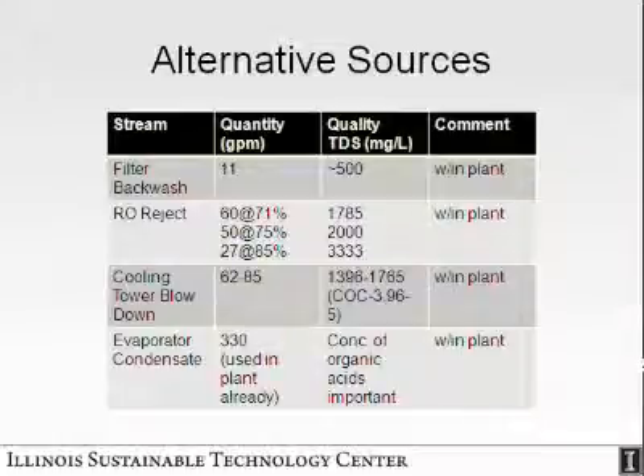The cooling tower blowdown — right now we have about 62 to 85 GPM depending on how we operate. If we operate it really efficiently, the TDS will go up to about 1765 milligrams per liter. If you operate less efficiently, you'll get about 1396.